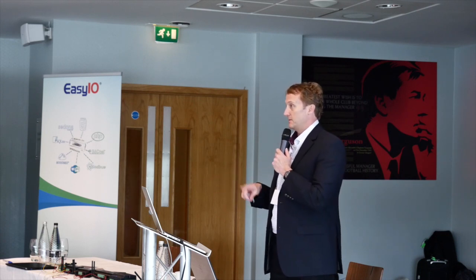I can't tell you how many times we have had problems with manufacturers' VAV controllers where the VAV actuator is physically mated to it, and you can't remove it. There's no way to uncouple it, and it just won't fit in the manufacturer's VAV. I mean, that happens all the time, right? And so you would be forced to buy the manufacturer's different controller that doesn't have an actuator, get the actuator separate, so you're losing that bundle, the economies of scale of bundling it, right? Well, in this way, their approach is they're simply going to start with a two-piece bundle right off the kicker. So that is going to solve a tremendous amount of installation problems down the road.